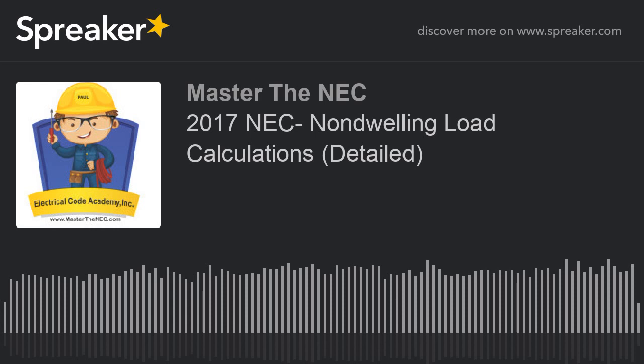Now, if the load is just a non-continuous load and we've got something that's not encompassed in this list of everything we just went through, and it's still on the drawings, and we look at it and go, God, what category does that apply to? I didn't really touch that in anything that we did. Look at its appliance, look at its value, calculate out a VA, and if it's non-continuous, you just take it at whatever its VA is, and you add it right here. And you add all of them up right here in step 14.